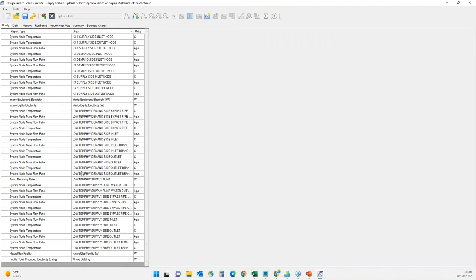C# and Python can be used to pre-process and post-process simulations, adding new EnergyPlus system components not yet included in Design Builder HVAC options, modifying properties of existing system components in the IDF file before simulation, and post-processing results to create bespoke reports. EMS on the other hand provides custom simulation runtime control to override selected aspects of standard EnergyPlus behavior. EMS used in detailed HVAC can range from a simple script to control HVAC start time based on outside air temperature to more complex operation schemes controlling multiple HVAC components using numerous sensors.